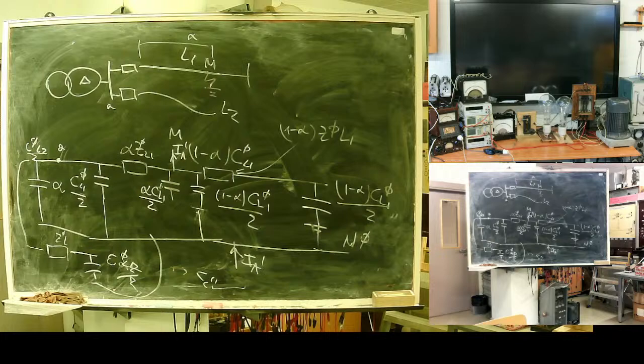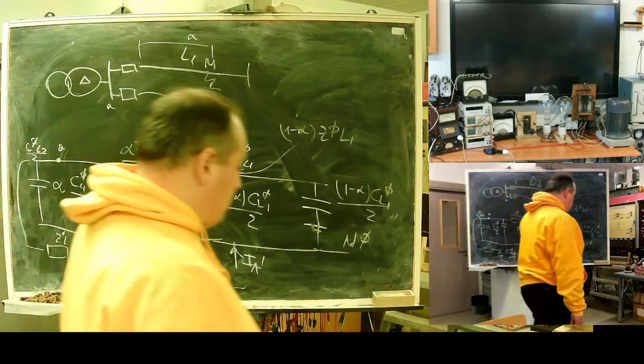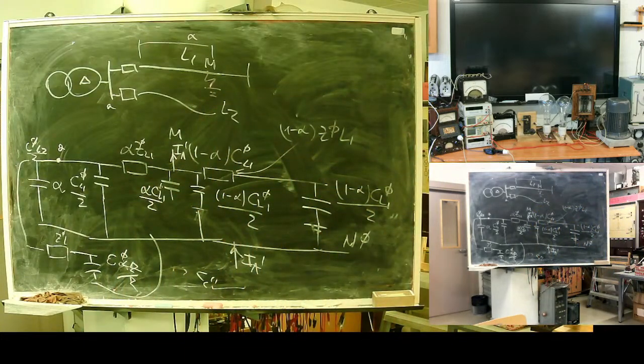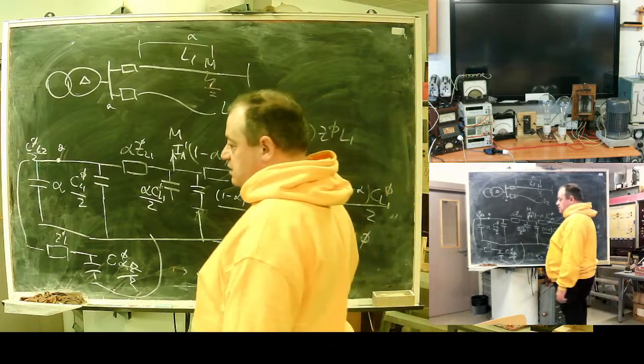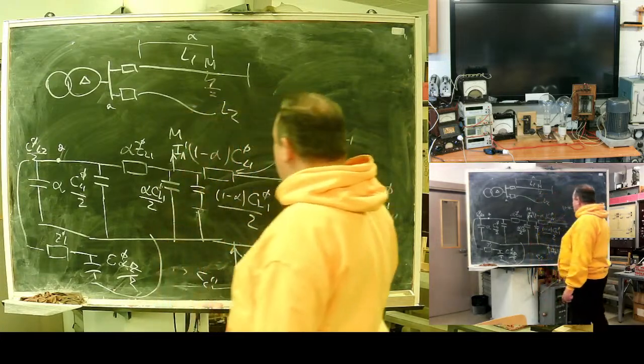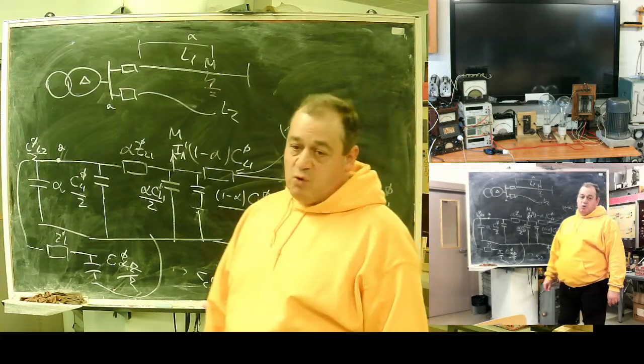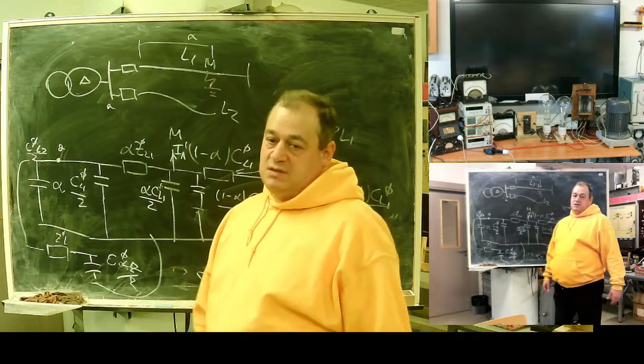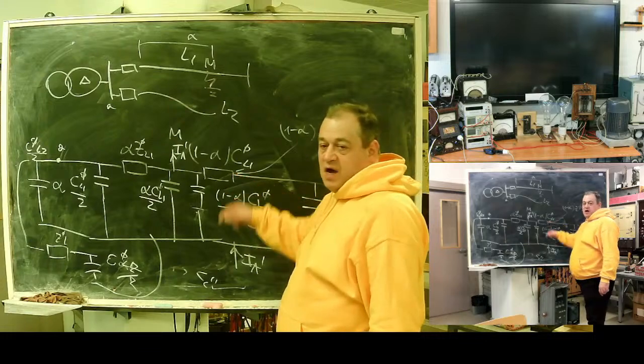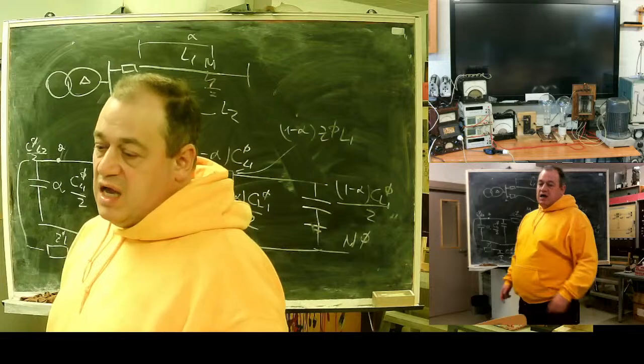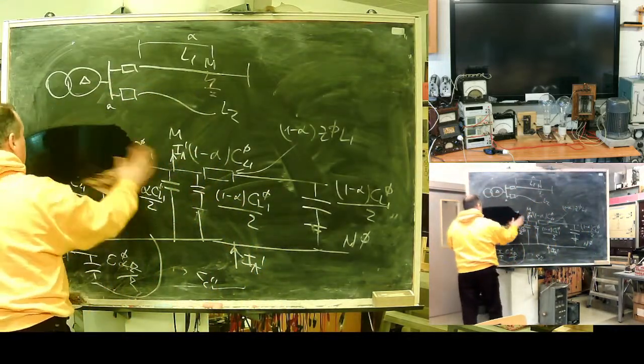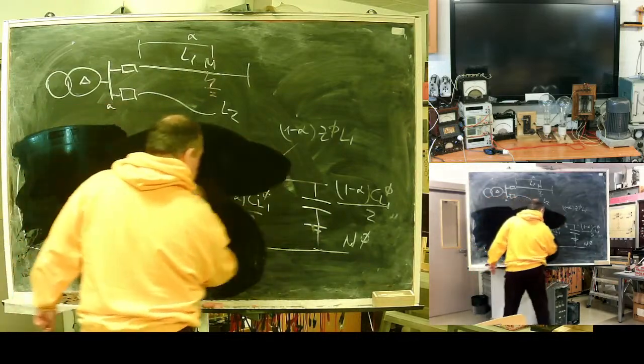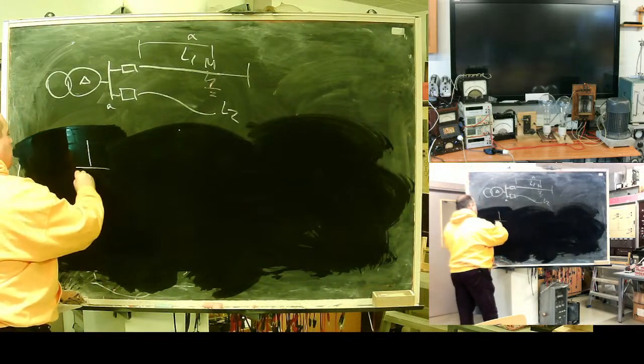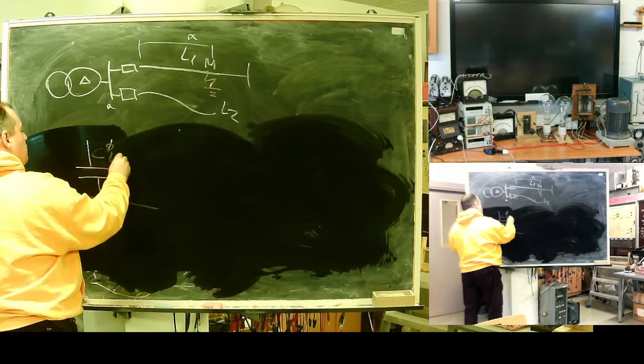Here is a precise model of this network, only zero sequence. But I draw it once just to represent. There is one moment. These capacitances are relatively small, and the resistance they introduce, its absolute value, is much higher than the line resistance. Meaning I can use a simplified schematic. It's absolutely adequate: C0 L2, point A where the buses are.